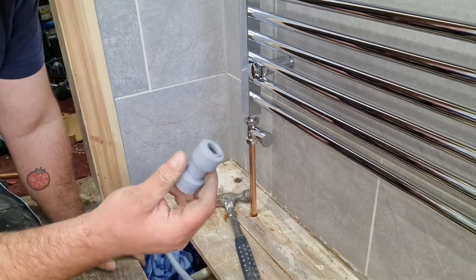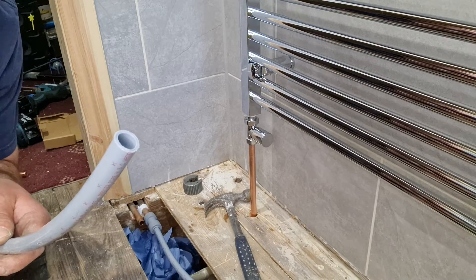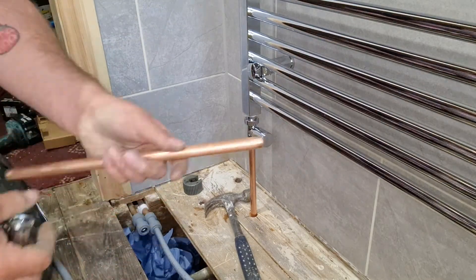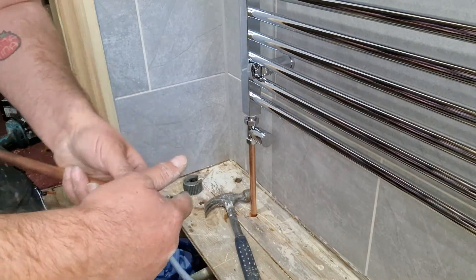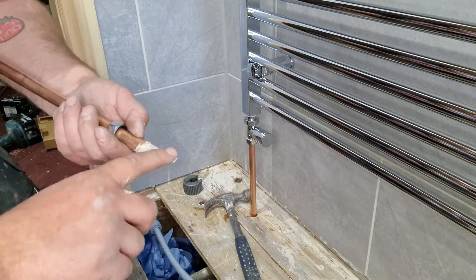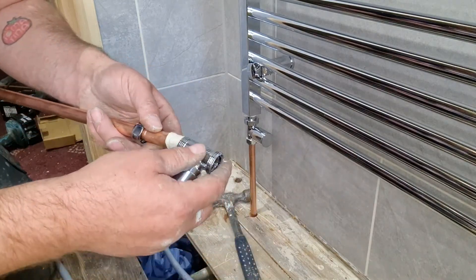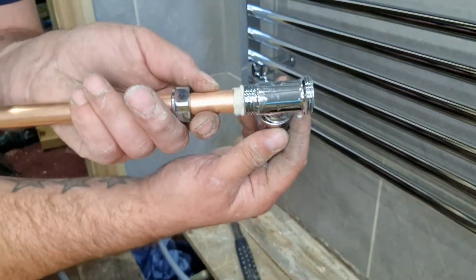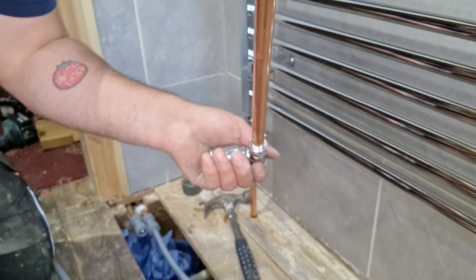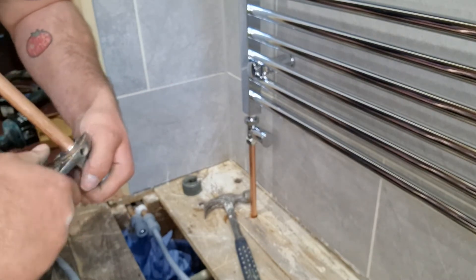So again, HEP socket. If you're putting HEP fittings onto copper, you won't need the insert — you only need the insert into the end of the plastic. HEP socket, push it on like so. Put your next bit of pipe, your next valve — literally repeat the process. Some paste. Get your valve back. You can see how it squirts out. Once you nip it all together, once the olive squashes to the pipe, it will create a really good seal. Just nip it up, don't have to be mega tight, just as tight as you can get it by hand.